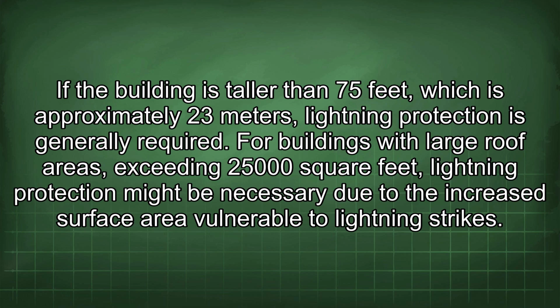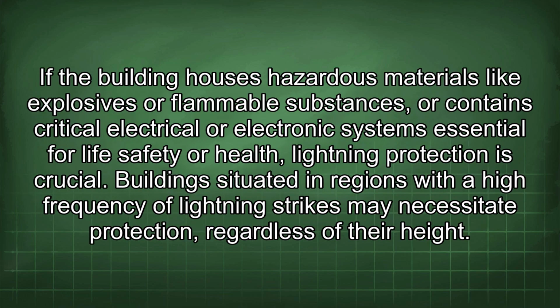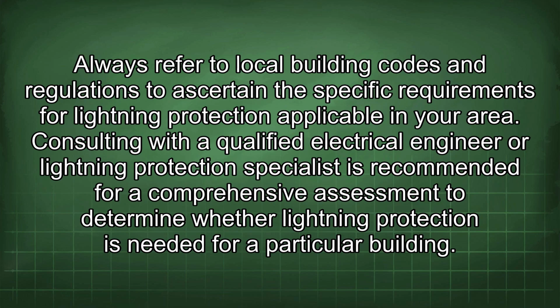For buildings with large roof areas exceeding 25,000 square feet, lightning protection might be necessary due to the increased surface area vulnerable to lightning strikes. If the building houses hazardous materials like explosives or flammable substances, or contains critical electrical or electronic systems essential for life safety or health, lightning protection is crucial. Buildings situated in regions with a high frequency of lightning strikes may necessitate protection regardless of their height. Always refer to local building codes and regulations to ascertain the specific requirements for lightning protection applicable in your area. Consulting with a qualified electrical engineer or lightning protection specialist is recommended for a comprehensive assessment to determine whether lightning protection is needed for a particular building.